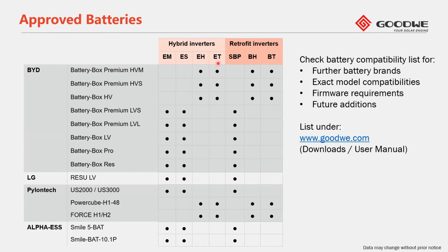When we're looking at the hybrid ET inverter, which is the DC coupled 3-phase high voltage inverter, we are compatible, as you can see, with the battery box from BYD, which is the HVM, and the HVS batteries, which are the new batteries that they released towards the beginning of last year, but took a while to get here to Europe. We're also compatible with the older HV battery box, which may still be on the shelves of some installers or distributors in Europe. Moving further down, in the ET range we're also compatible with Pylon Tech, which is either the Powercube H1-48 or the Force H1H2, which is also Pylon Tech's new high voltage battery, released towards the middle to end of last year.